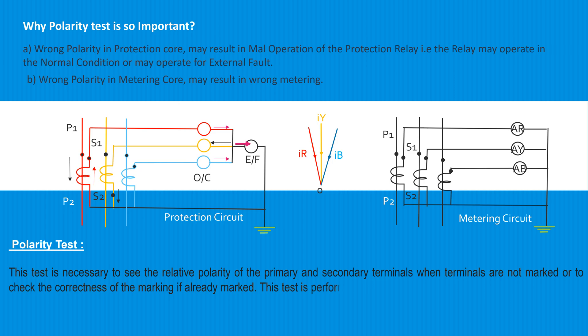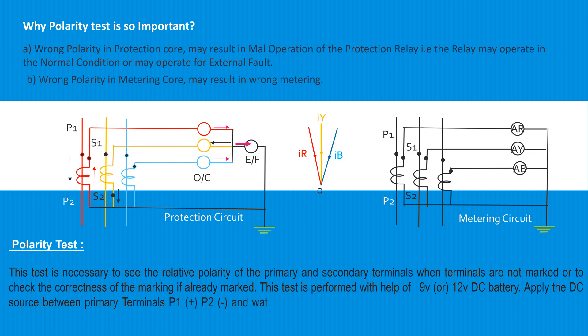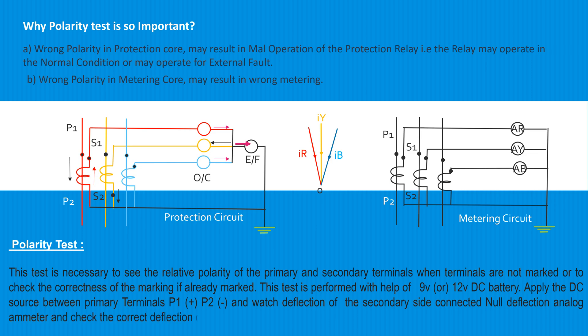This test is performed with the help of a 9-volt or 12-volt DC battery. Apply the DC source between primary terminals P1 positive and P2 negative, and watch the deflection of the secondary side connected null-deflection analog ammeter, and check the correct deflection of the meter and compare with the polarity mark.